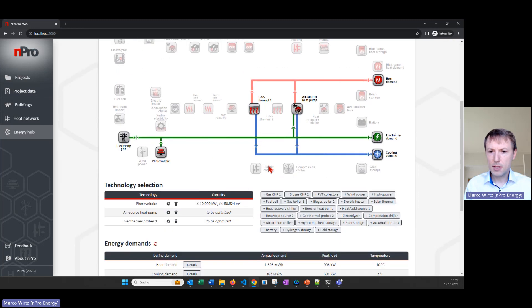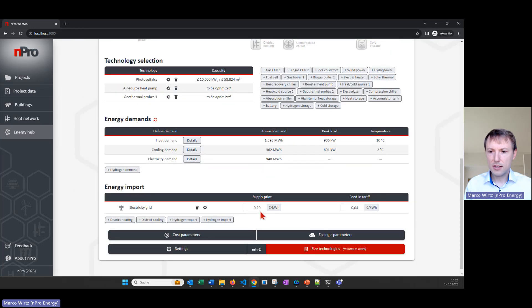Looking at the economic parameters, we can define the electricity price and investment costs for all technologies. Then I click 'Size Technologies' to get the optimal system configuration — how much heat pump capacity and how much geothermal capacity is needed. The result is roughly a 50/50 split: geothermal probes handle the base load and the air source heat pump handles the peak load. We also get the optimal PV sizing.